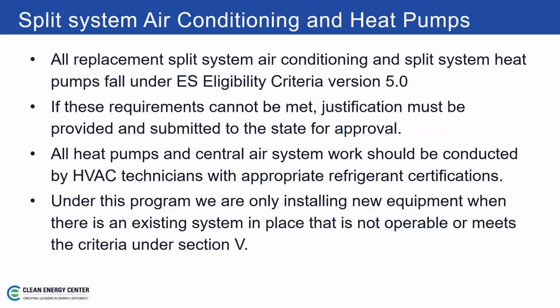All right. So split system air conditioning and heat pumps. Now we're moving away from the window air conditioners or room air conditioners, and we're going to talk about split system air conditioning and heat pumps. All replacement split system air conditioning and split system heat pumps will fall also under the Energy Star eligibility criteria listed in the document that you have or should have under version 5.0. If these requirements cannot be met, justification must be provided and submitted to the state for approval.